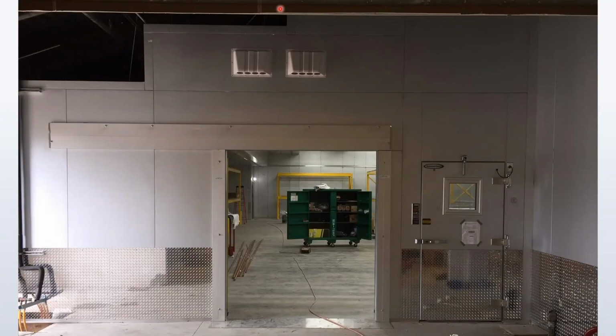Here we can see a larger warehouse freezer. We have a standard man door on the right-hand side, while the opening in the center is for a sliding door. The 2 rectangles above the sliding door are heated pressure relief vents. While they vary in size and quantity, a freezer always requires a pressure relief vent. This is done to equalize the pressure inside a walk-in so that the doors can operate properly. Something to look at on this walk-in though is the way the roof steps up as you go from left to right.